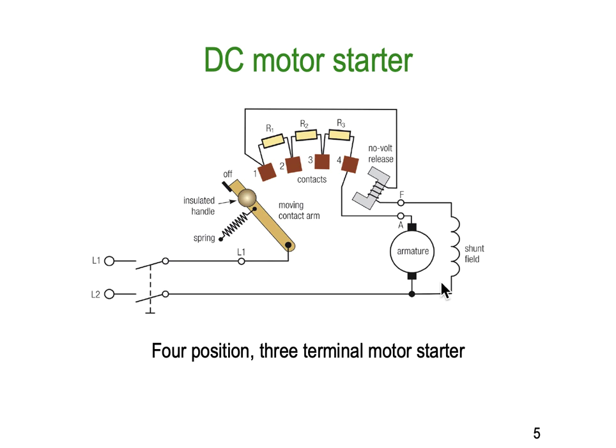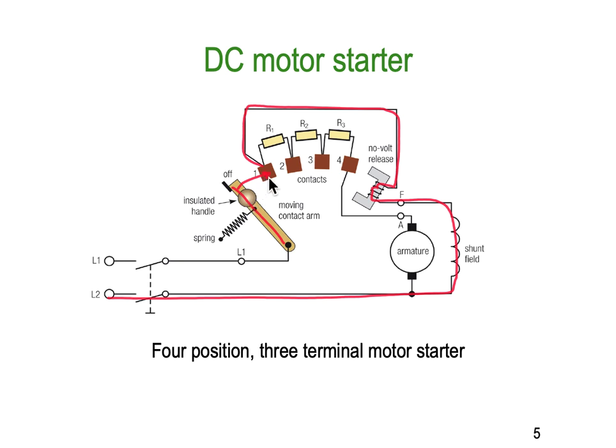So how can we go about doing that? This is a four-position, three-terminal DC motor starter. You have a lever arm connecting the supply to the armature. When we move the arm across, current goes through the release catch into the shunt field and back to the supply. We also have current feeding to the armature, but it has to loop through all three of those resistors.